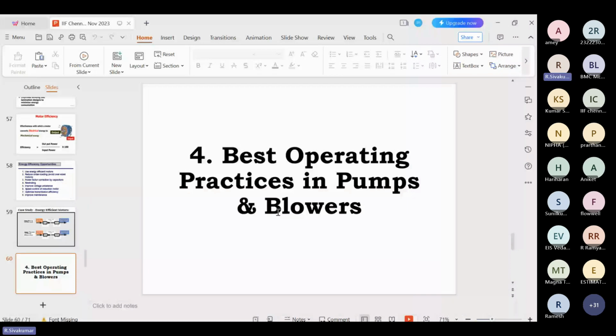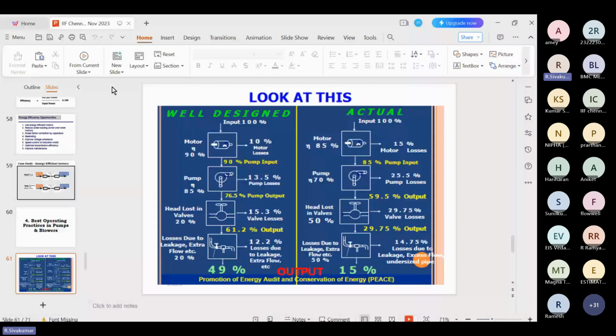See the pumps. As per the well design, the input energy given is 100%. Finally, the output is 49% only. The useful energy transmitted into the fluid power, that is the water power. Whereas in actual cases, many times this value will be 15 to 25% only. So this much potential is there compared to the motor. For pump applications there is a lot of energy that can be saved if the pump is properly designed and properly operated.